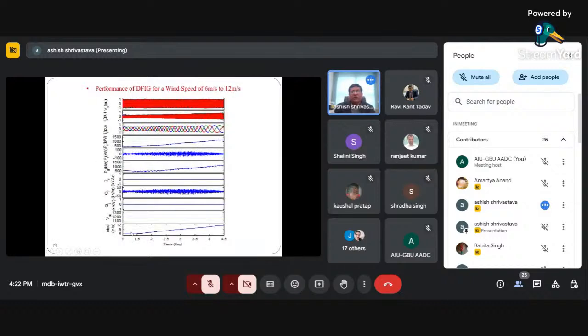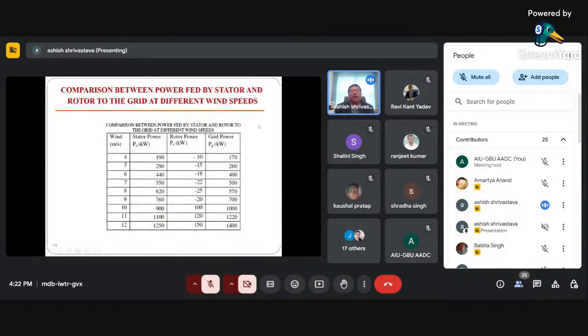So if you vary between 6 meter and 12 meter per second, your current magnitude is increasing because you have increased the speed, but your current remains perfect. All three phase currents are maintained perfectly sinusoidal. If you zoom this portion, it looks perfectly sinusoidal, which ensures your input power factor is maintained on the AC side. So this is our requirement, that power quality should be maintained.